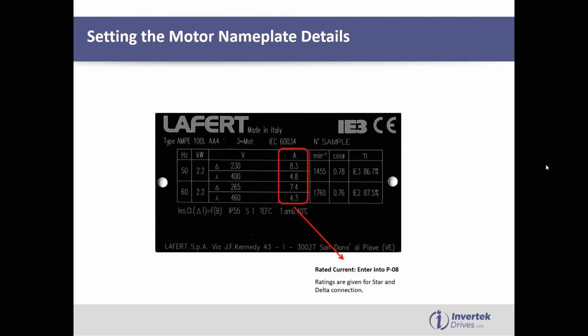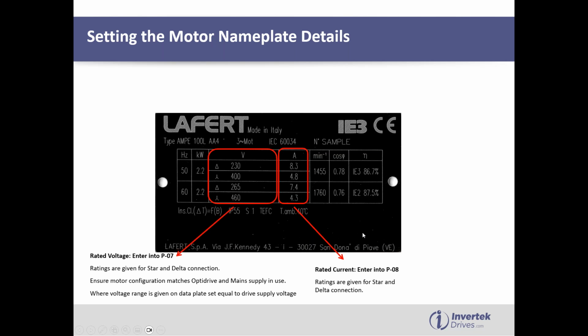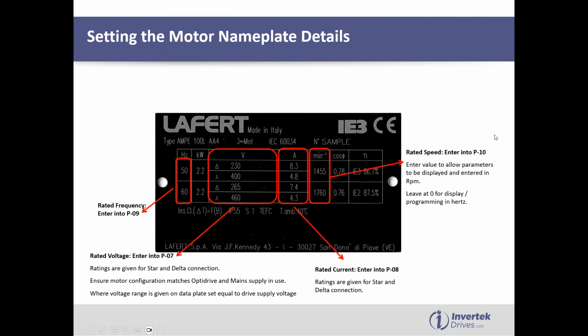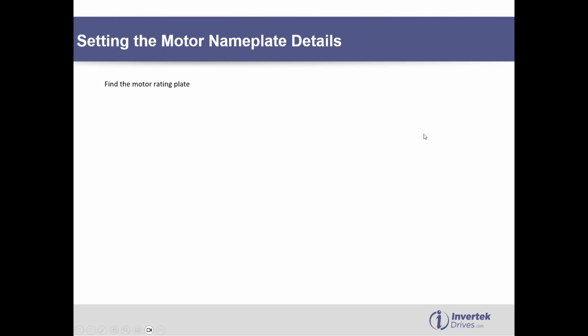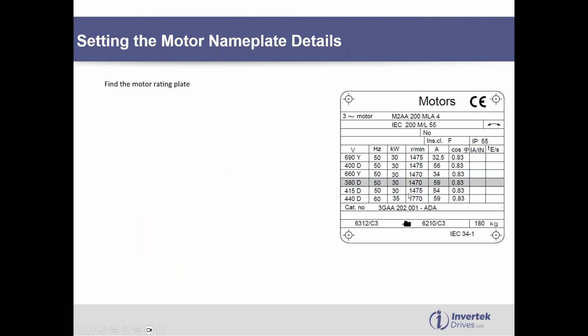220 volt 50 hertz and 440 volts 50 hertz in Jamaica. Excellent. Because with these Lafert motors, it's nice and simple. You have just a few ratings on there. These are just the parameter numbers that we put in on the drive. But with some other motor manufacturers, you can have a lot more information on there.